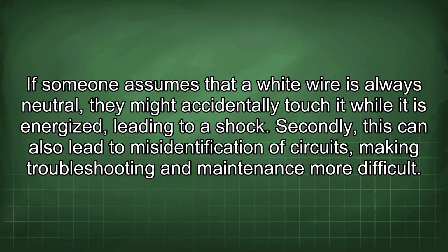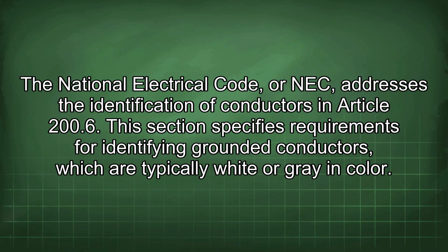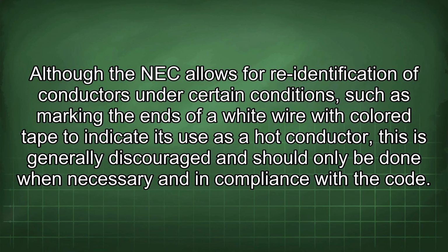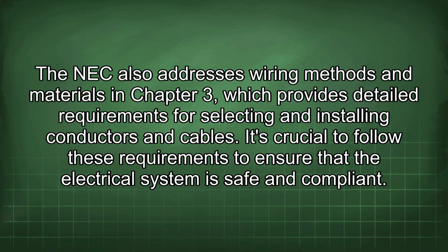Secondly, this can also lead to misidentification of circuits, making troubleshooting and maintenance more difficult. The National Electrical Code, or NEC, addresses the identification of conductors in Article 200.6. This section specifies requirements for identifying grounded conductors, which are typically white or grey in color. Although the NEC allows for re-identification of conductors under certain conditions, such as marking the ends of a white wire with colored tape to indicate its use as a hot conductor, this is generally discouraged and should only be done when necessary and in compliance with the code. The NEC also addresses wiring methods and materials in Chapter 3, which provides detailed requirements for selecting and installing conductors and cables. It's crucial to follow these requirements to ensure that the electrical system is safe and compliant.